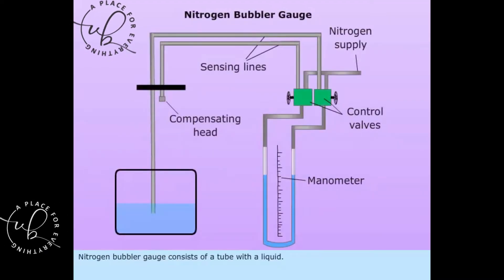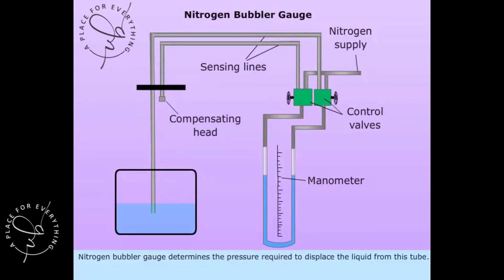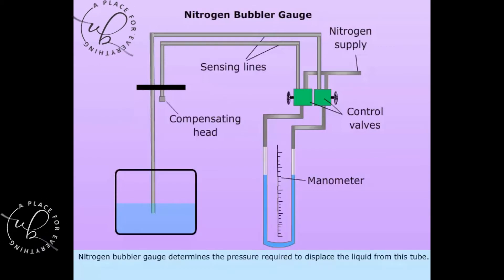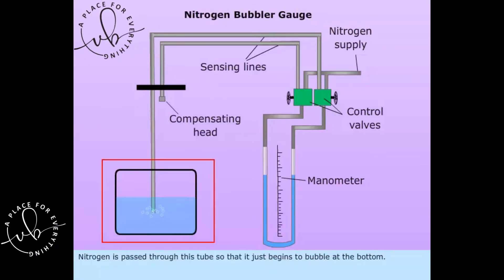Nitrogen bubbler gauge consists of a tube with a liquid. Nitrogen bubbler gauge determines the pressure required to displace the liquid from this tube. Nitrogen is passed through this tube so that it just begins to bubble at the bottom. The prevailing pressure is the function of liquid density and liquid level.